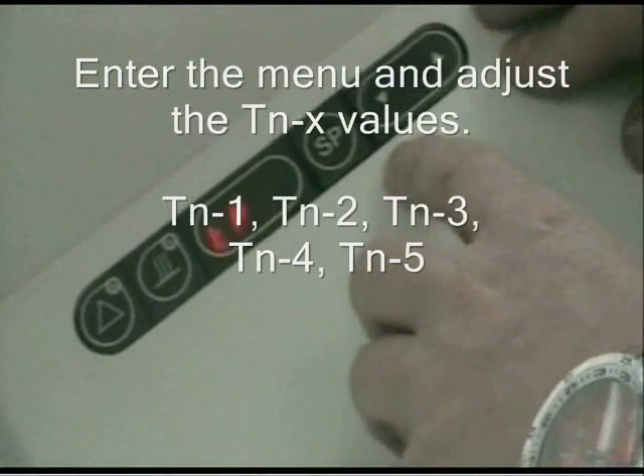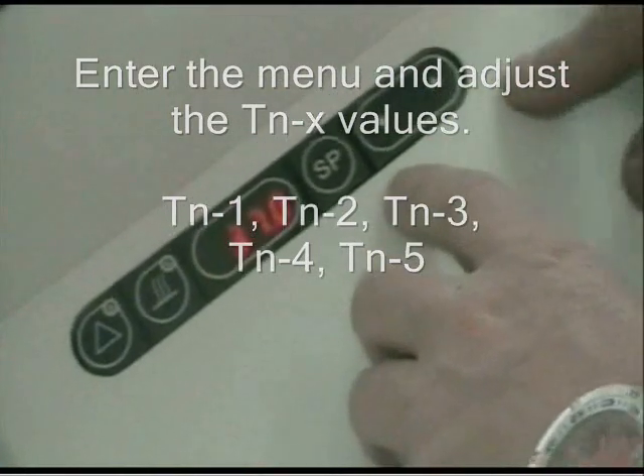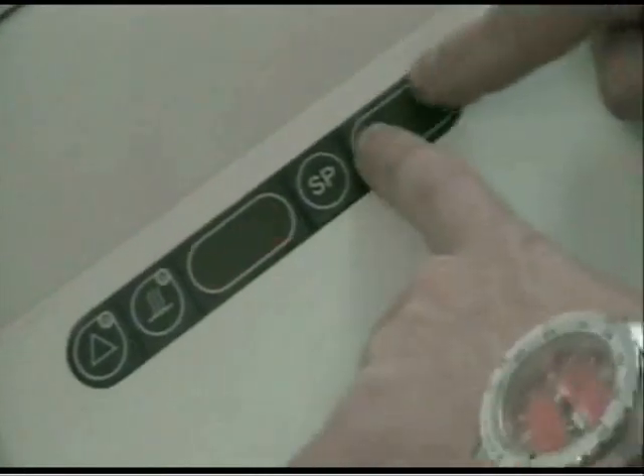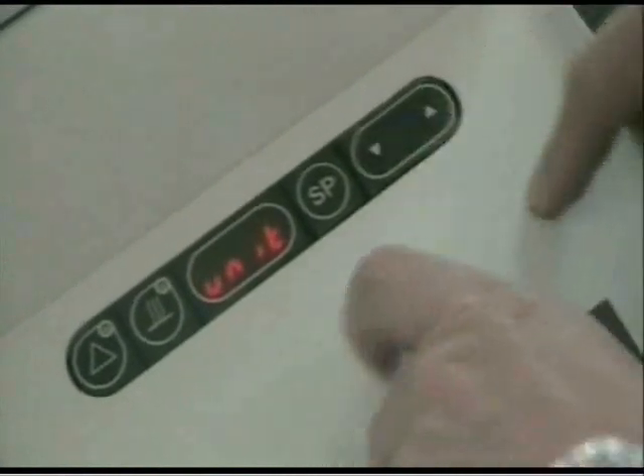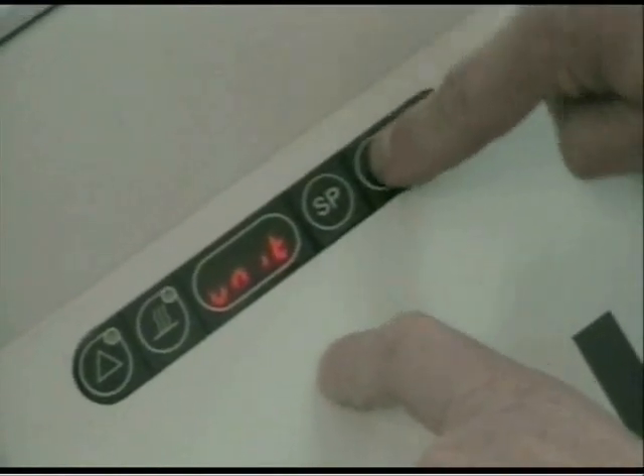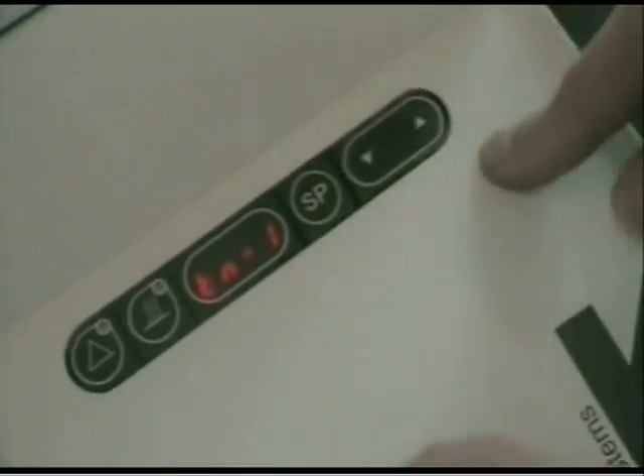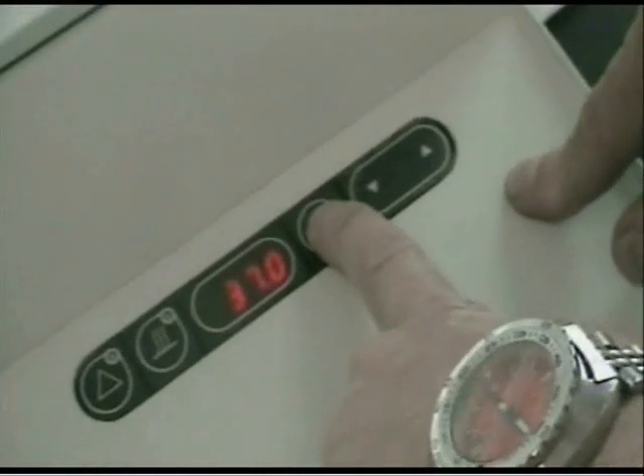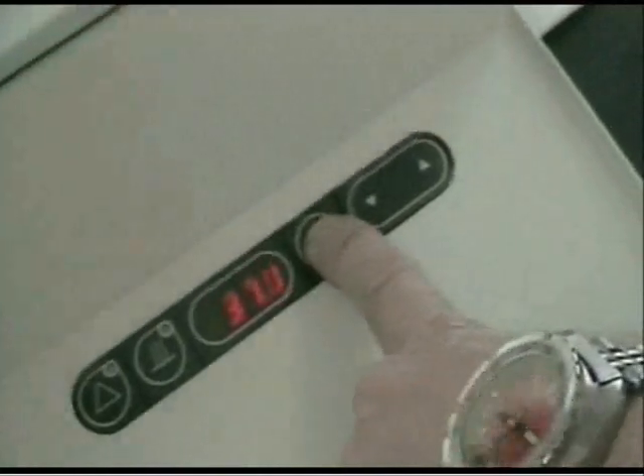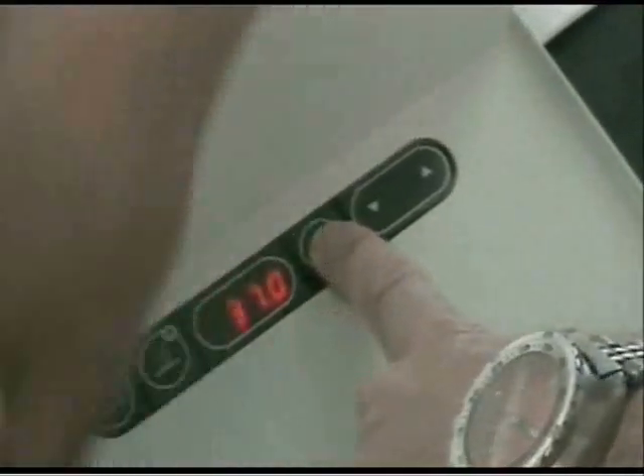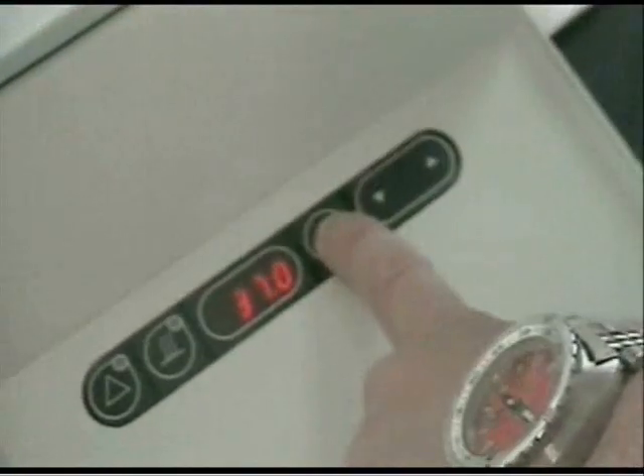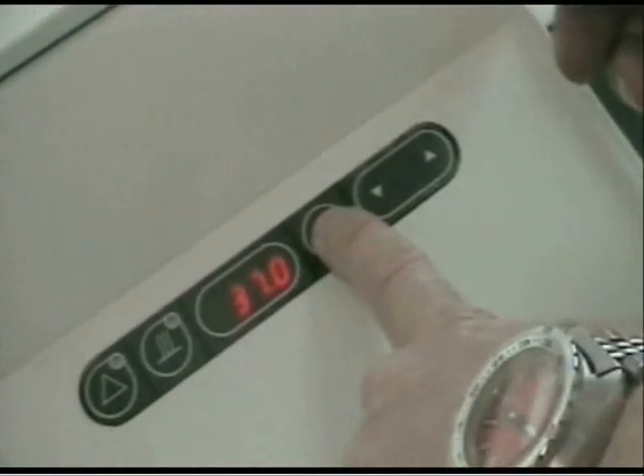So now we will adjust the tune values inside the menu. I enter the menu by pressing and holding the arrow keys for approximately 3 seconds. Shifts to unit. And then I scroll down in the menu until I find the first tune 1 value. It's here. Then I press the SP button. This is the current reading of what the incubator thinks is the temperature on this zone, which is 37 degrees, but obviously incorrect according to our measurement.